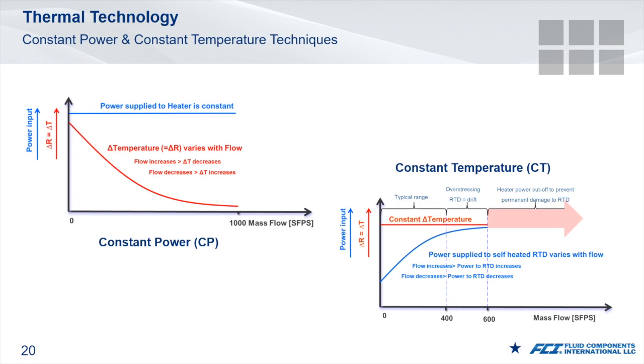Constant temperature is when the current to the RTD is varied to maintain a temperature differential. The amount of current used is proportional to the mass flow. Newer hybrid designs are also available. These hybrids marry both constant power and constant temperature capabilities into a single instrument. Since each technique has its own advantages and disadvantages, hybrids maximize the benefits of both.